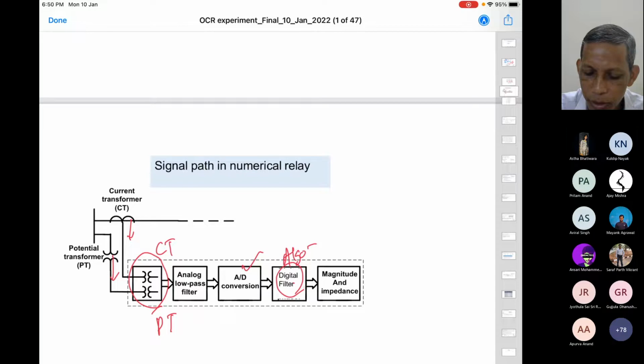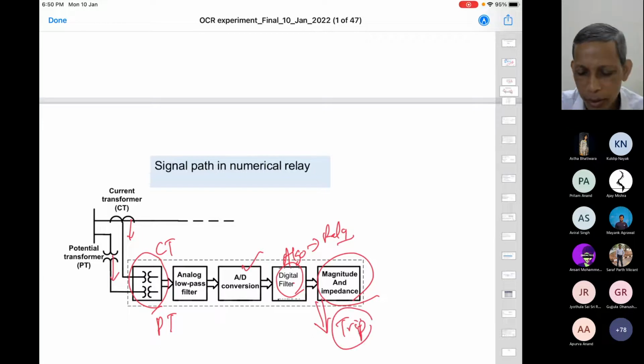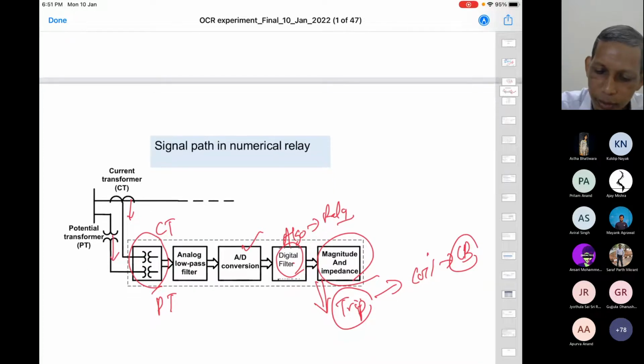Then comes the algorithm part. Which algorithm? The relay algorithm. What is that? The decision making process: the current is high, the voltage is low, and the differential current is substantial, this and that. That is a very simple way of talking about it, but it is not just that. It requires certain characteristic curves and so on to verify, and you can also compute the impedance, and from there you derive the trip decision. Now after deriving the trip decision, what will you do? It will communicate to the trip coil, the trip coil of what? For the circuit breaker opening. This is what is required from a particular relay.